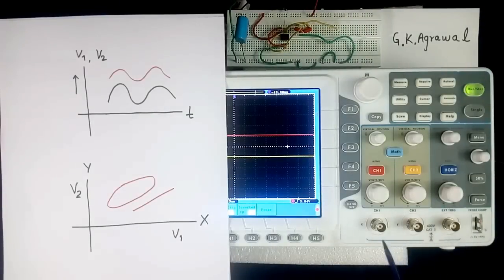These 2 are input. Here we have to give voltage input. It will not take current input. If you want to measure current, you have to convert current into voltage, using some probe or some other method. And then give voltage here.